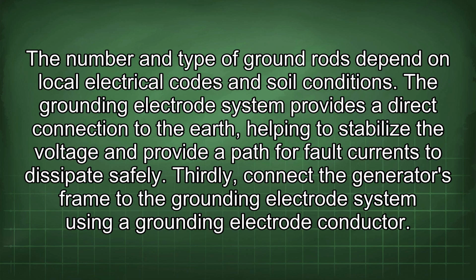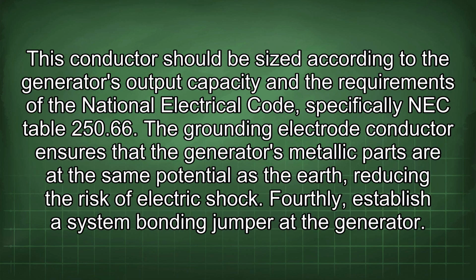Thirdly, connect the generator's frame to the grounding electrode system using a grounding electrode conductor. This conductor should be sized according to the generator's output capacity and the requirements of the National Electrical Code, specifically NEC Table 250.66. The grounding electrode conductor ensures that the generator's metallic parts are at the same potential as the earth, reducing the risk of electric shock.